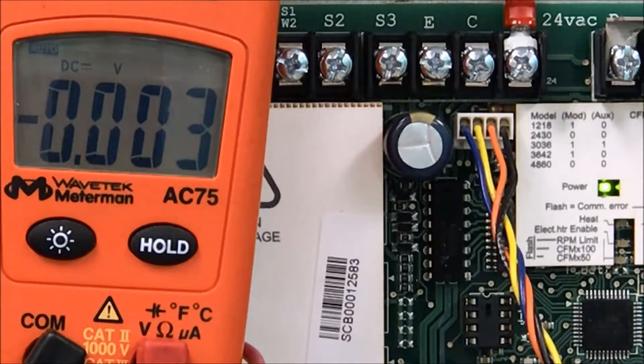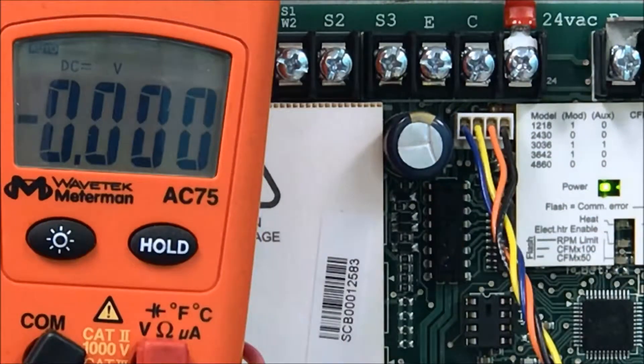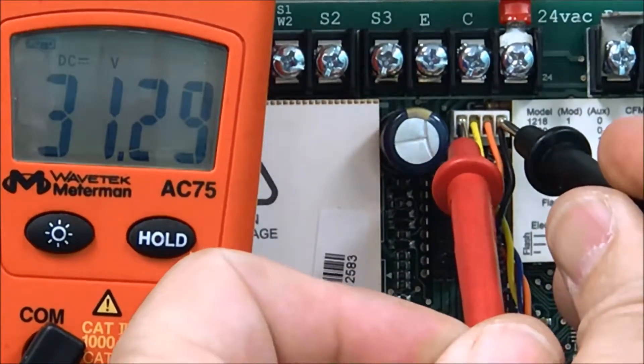So after ensuring that your motor does spin free, the first test we're going to do on the board is we're going to check between the blue wire and the black wire on this connector. Between this blue wire and this black wire, we should have 30 volts DC.